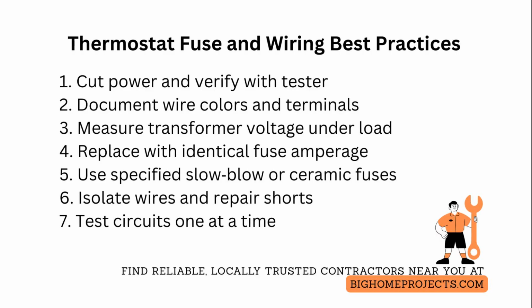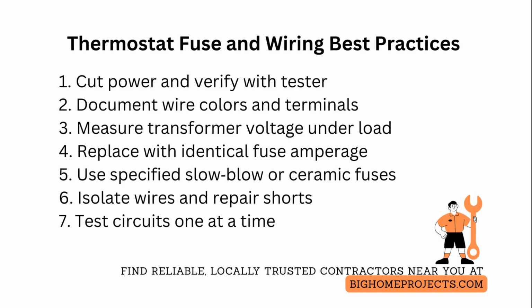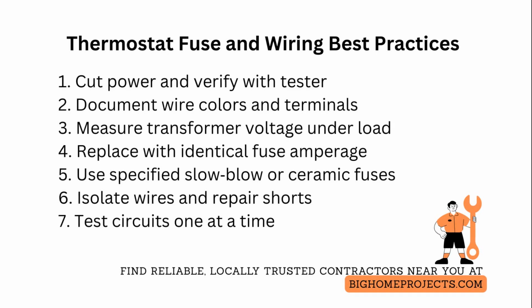When testing, reconnect only one control circuit at a time and watch for fuse blow while monitoring current draw with a clamp meter. If current exceeds the fuse rating immediately, stop and troubleshoot wiring, not the fuse.